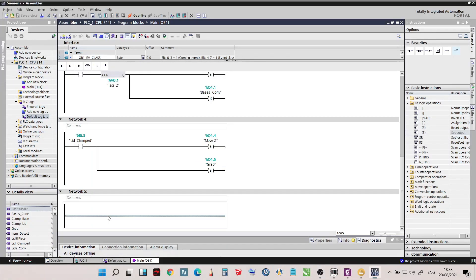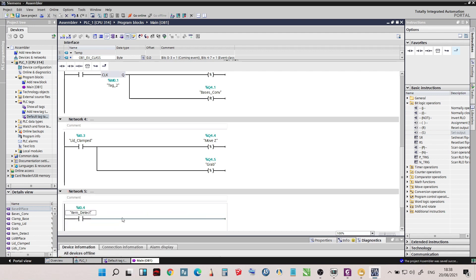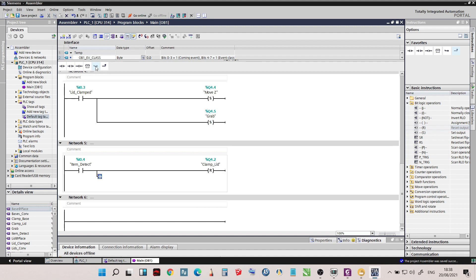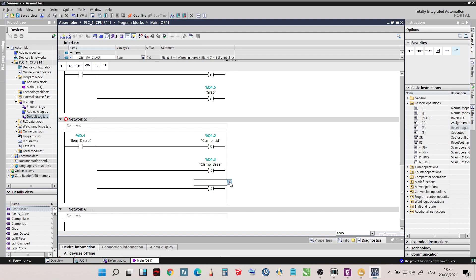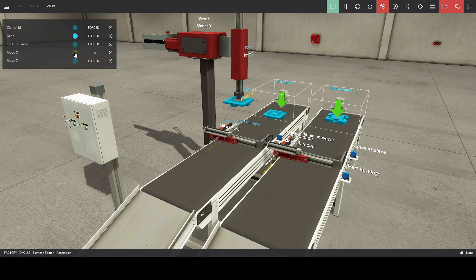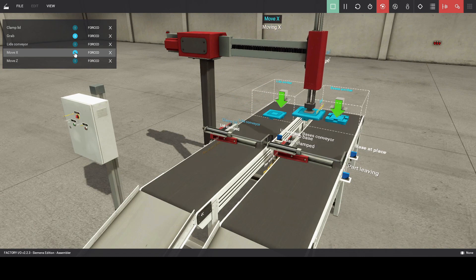For the next network, let's add an open contact for item detect. When item detect energizes, clamp lid will reset, and so will clamp base, while move Z will go back to its original position. For the output, we will add 3 reset functions — it will reset clamp lid, clamp base, and move Z. Now when the arm goes up with the product, the next sequence is to move the arm towards the base conveyor, so let's add an output set function for move X.